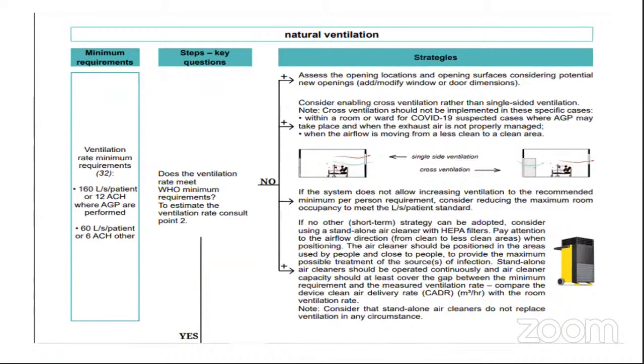In case no other short-term strategy is possible, we will have to rely on standalone air cleaners working with HEPA filters. They should be close to the people for possible treatment of the source of infection. They should be running constantly, without a gap, and they should have a clean air delivery rate according to the room ventilation rate. So these are a few of the strategies that can be followed if the ventilation rate is not meeting the WHO minimum requirement.